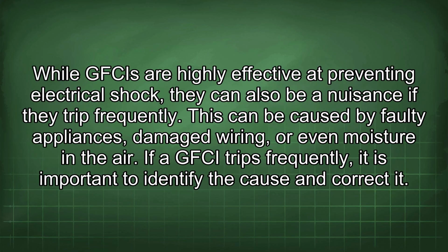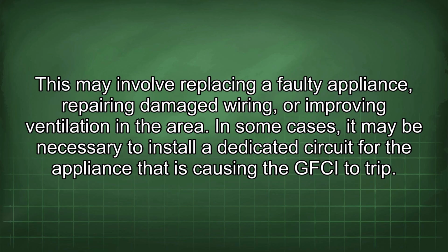While GFCIs are highly effective at preventing electrical shock, they can also be a nuisance if they trip frequently. This can be caused by faulty appliances, damaged wiring, or even moisture in the air. If a GFCI trips frequently, it is important to identify the cause and correct it. This may involve replacing a faulty appliance, repairing damaged wiring, or improving ventilation in the area.